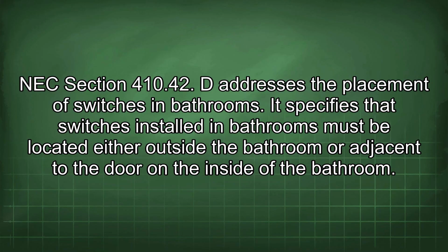NEC Section 410.42(D) addresses the placement of switches in bathrooms. It specifies that switches installed in bathrooms must be located either outside the bathroom or adjacent to the door on the inside of the bathroom.